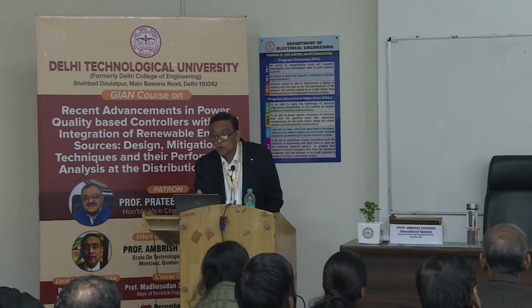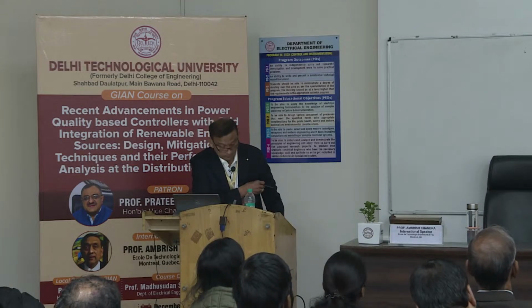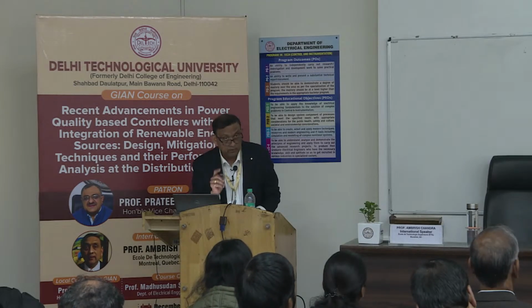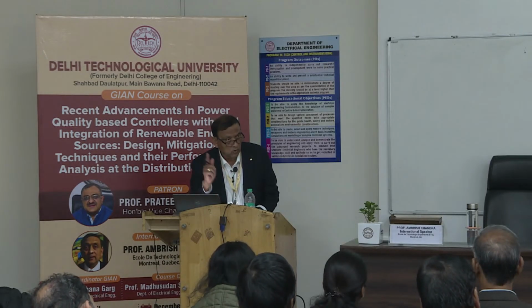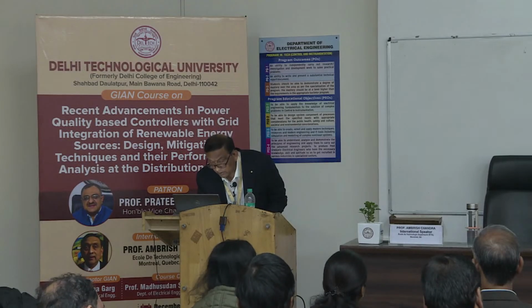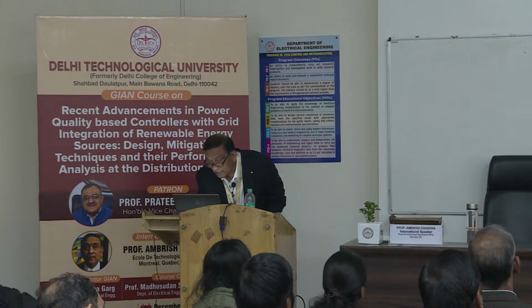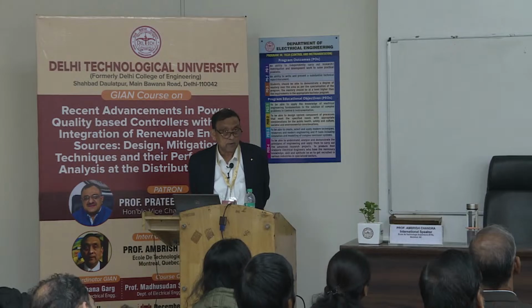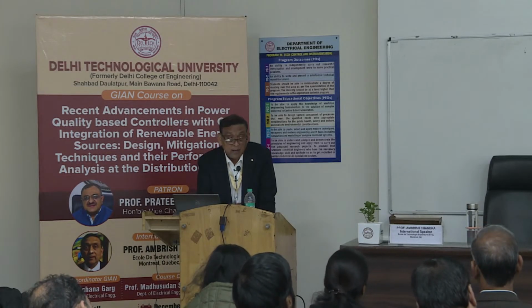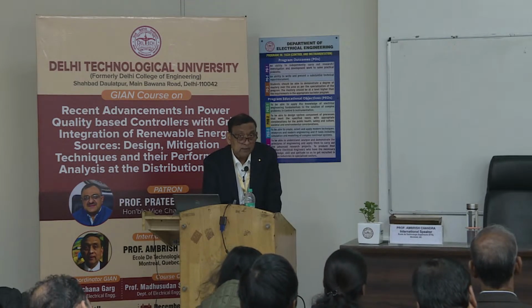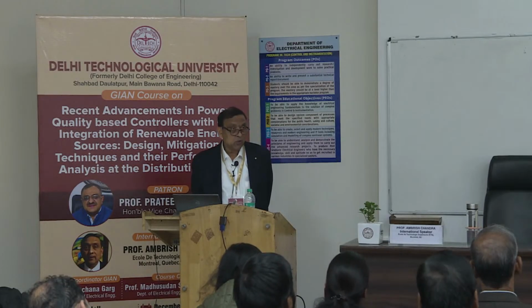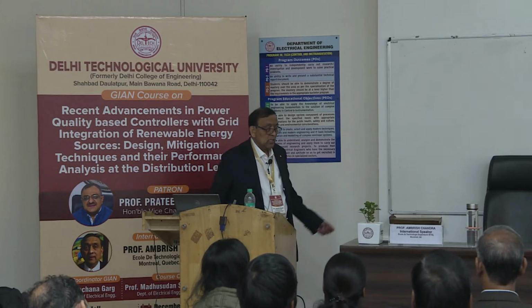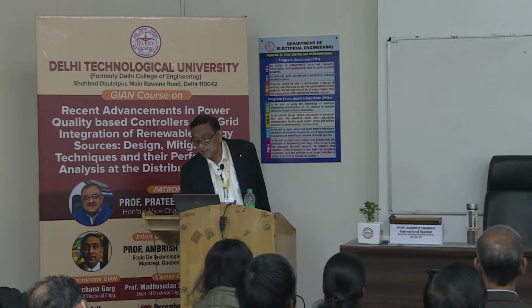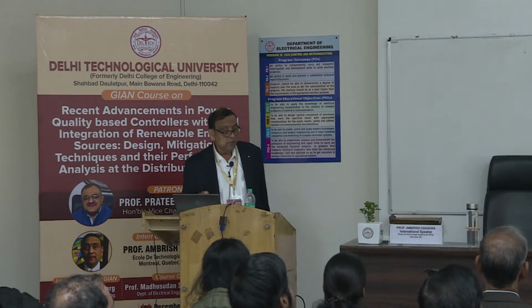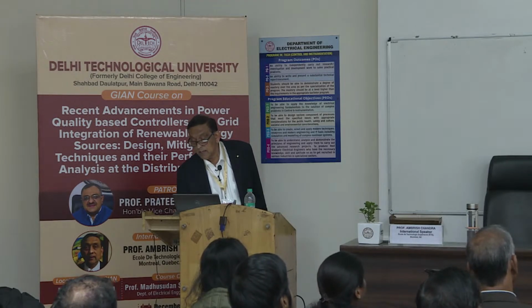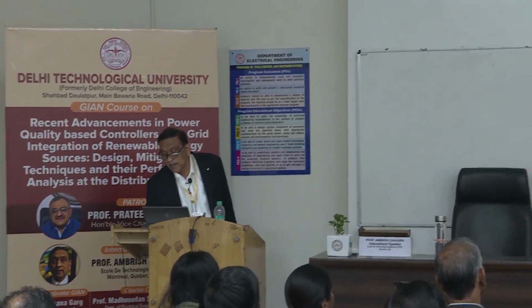Telephonic interference is caused by the harmonics. Please tell me when I have to stop for them, okay? But I will continue. Large neutral current consisting of third harmonic. So what is the third harmonic? It is a zero sequence harmonic. So what is this? There are 3 currents coming, IA, IB and IC.